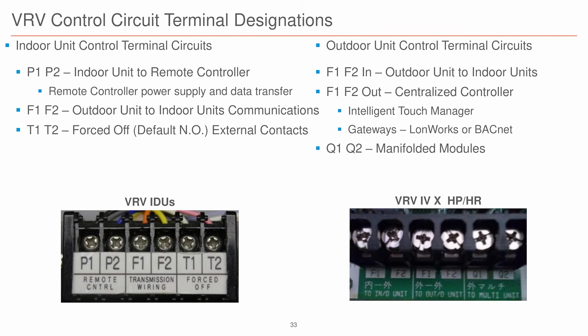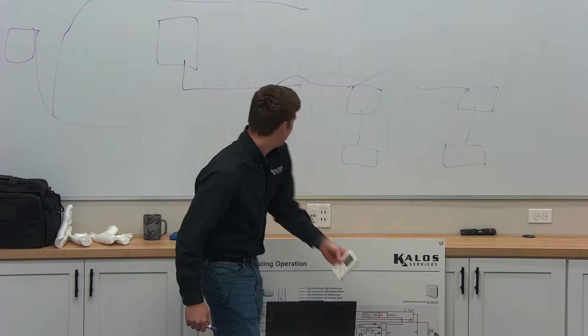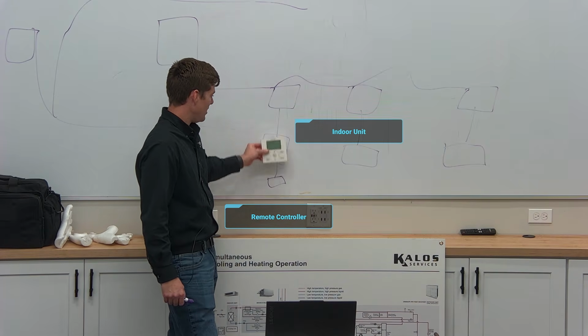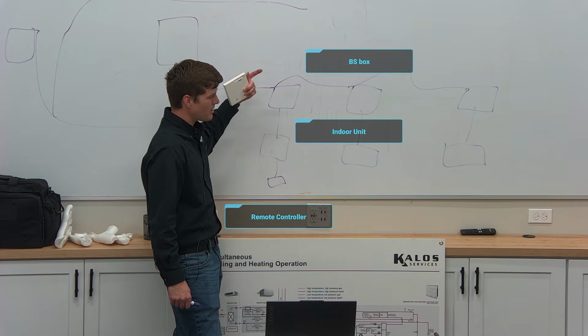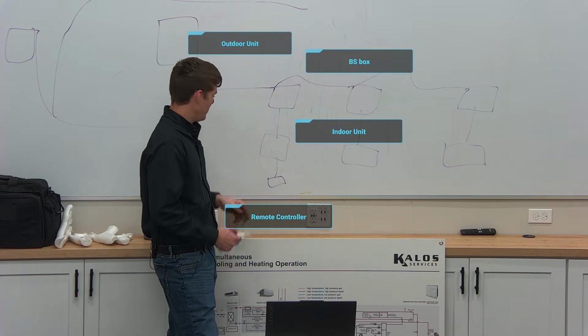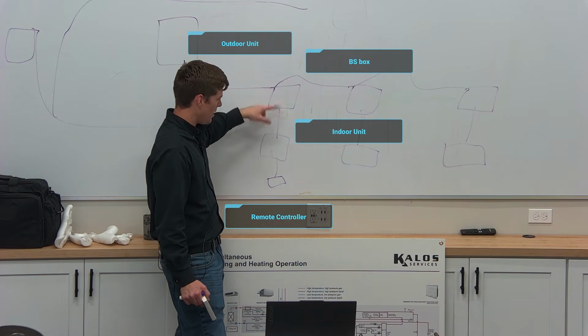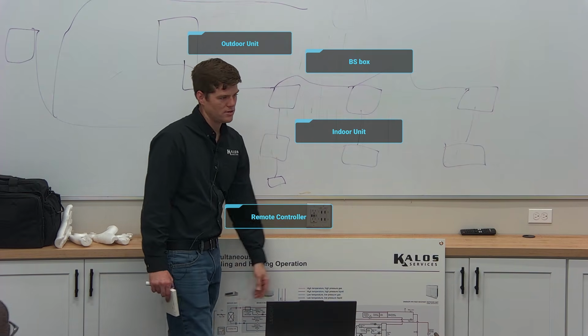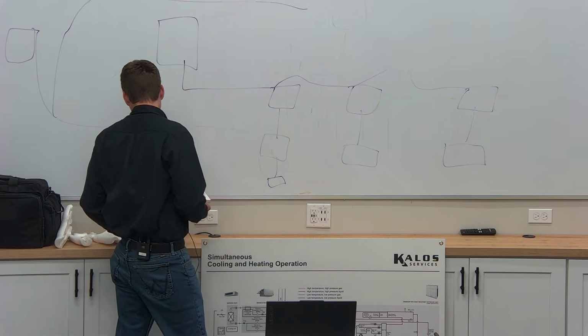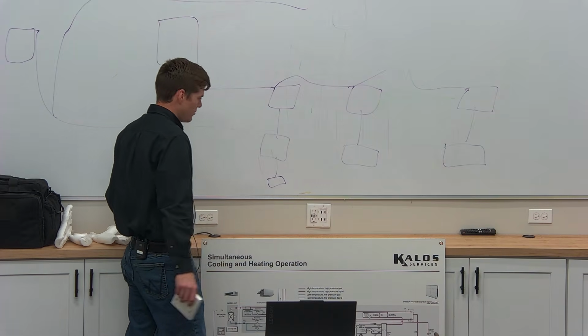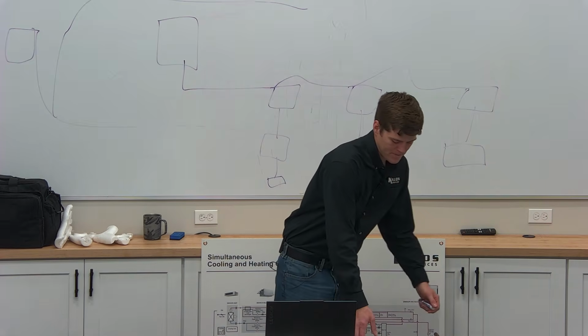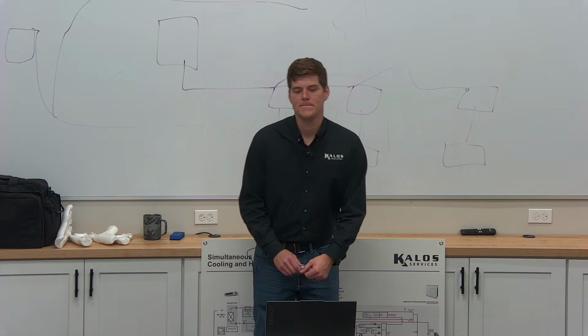You'll notice here we have F1, F2, P1, P2, T1, T2. P1, P2 is remote controller, right? Let's add another layer to this, right? Remote controller to indoor unit to BS box to outdoor unit. This is one line of communication, this is one line of communication, and the rest are on one line of communication. Why is it we use a 2-wire communication system instead of 24 volts for VRF? Anybody? Is it shielded?